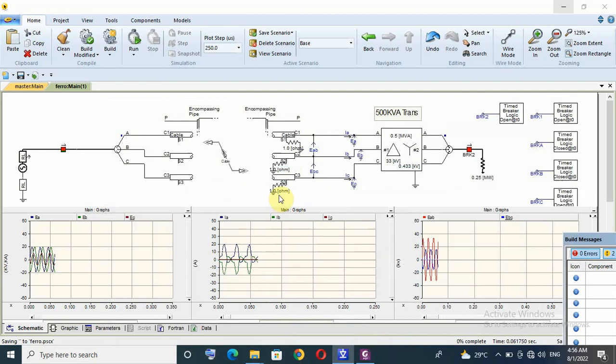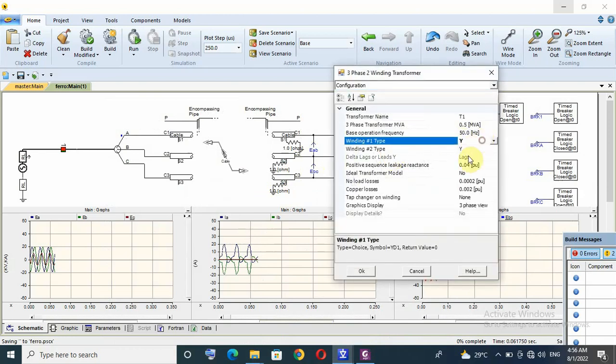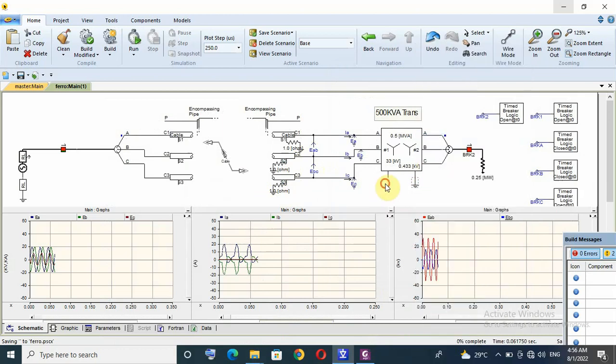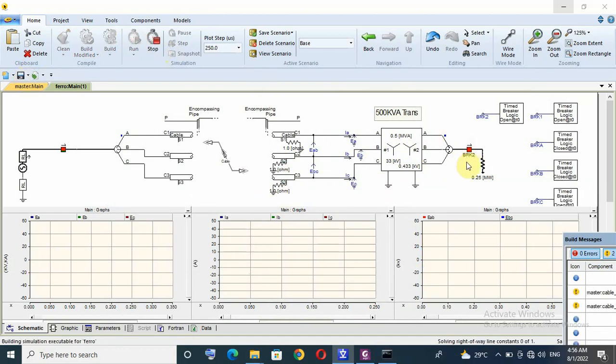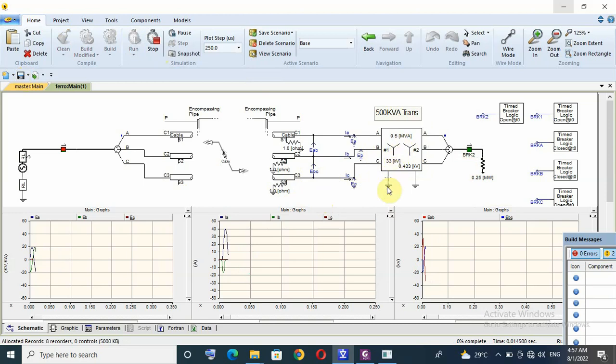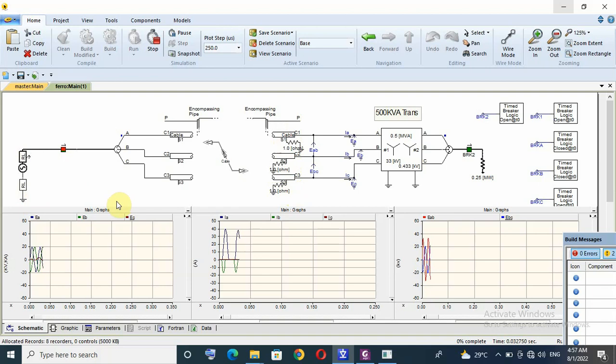Next scenario I want to test this configuration with primary star and this is star, the star point or neutral point of star earthed. So let us test and we don't have load, you see this breaker should be in green that means off state. Because of primary side is star earthed and our cable earthed, that means the capacitance between core to earth and our supply also earthed, this condition not fulfill the condition of ferro resonance phenomena to happen.